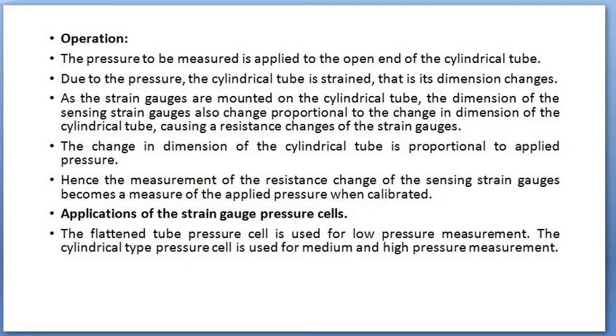Hence the measurement of the resistance change of the sensing strain gauge becomes a measure of the applied pressure, which can be calibrated. In our applications, this cylindrical type pressure cell will be used for medium and high pressure measurement. Using the same concept but with a flattened tube instead of cylindrical, you can make use of it for low pressure measurement.